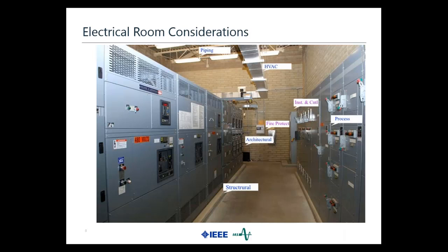Then on the floor, you notice that the MCC, the I&C panel, and the switch gear are all actually on what I call a housekeeping pad. I don't know where this picture actually is, I just found it on the internet, but a lot of plants I've been involved with over the years use a 4-inch pad to put the electrical equipment on, to keep water from getting into the bottom of the gear if there's a potential for flooding.